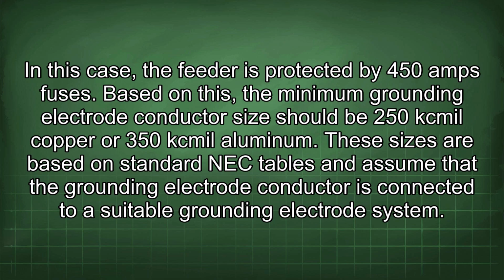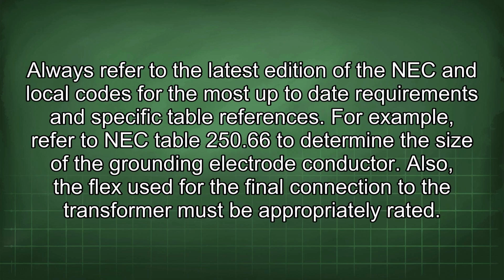These sizes are based on standard NEC tables and assume that the grounding electrode conductor is connected to a suitable grounding electrode system. Always refer to the latest edition of the NEC and local codes for the most up-to-date requirements and specific table references. For example, refer to NEC Table 250.66 to determine the size of the grounding electrode conductor.